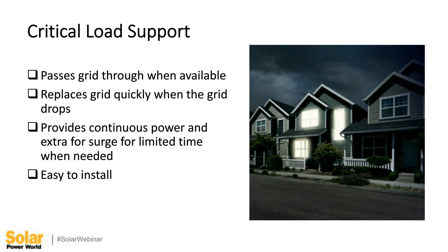As we talked about earlier, when you're running on your critical load, you've got your refrigerator. The power needed to run the motor at steady state is pretty low with the new energy efficient refrigerators. However, it still takes 2 to 3 times that power to get started. So you want to select your hybrid inverter to make sure that on the critical load, it doesn't just provide 5,000 watts, but can provide 6,000, 7,000, 8,000 watts or more for some period of time. Usually it doesn't need to be continuous, but it needs to be anywhere from 5 to 45 or 50 seconds to allow these surges to be managed.